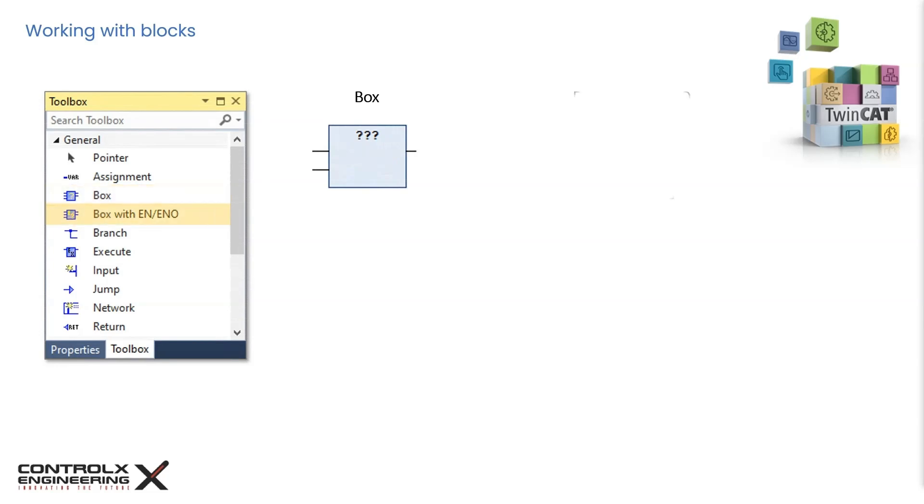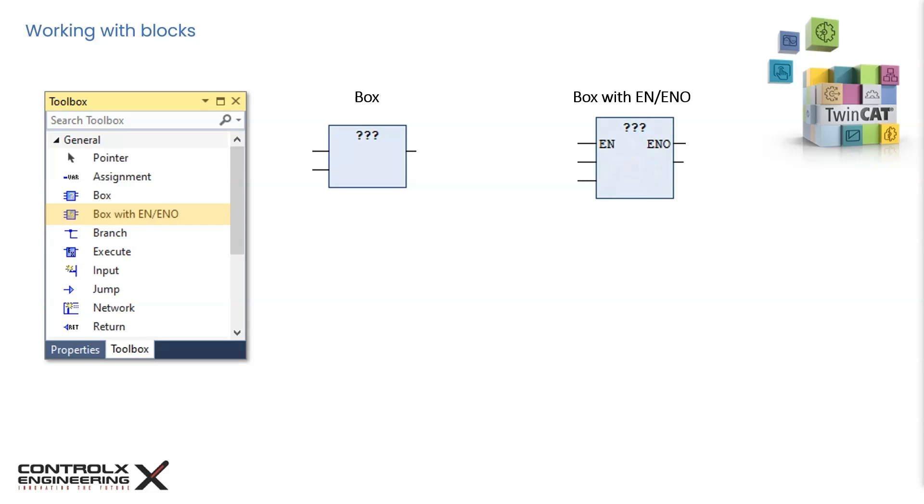There is also another item called box with EN slash ENO, which is the same generic box with additional input and output labeled as EN and ENO. This Boolean input EN can be considered as an enable input, and it controls the execution of this block. The operation defined in the box is only executed if the enable input is true, when the block is called. The ENO is the same enable input passed through as the output and can be considered as an enable output and used to tie to the enable input of the next block to its right as a daisy chain.